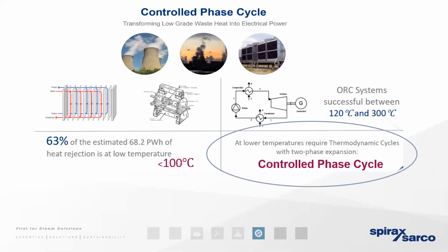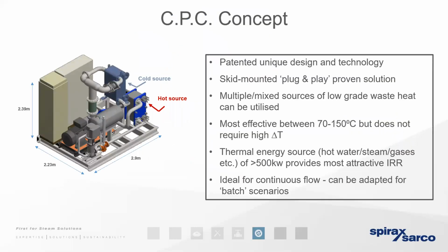So a CPC is basically a skid-mounted solution. It takes its temperature from the effluent stream, and it causes a phase change of refrigerant on the secondary side of the heat exchanger. This refrigerant is basically an expanding gas. As it expands, it turns a turbine to generate a small amount of electrical energy. And then the gas is cooled and condensed, and the cycle continues, and the effluent that's been reduced in temperature is then passed to waste, and the electrical energy just goes into the local network.